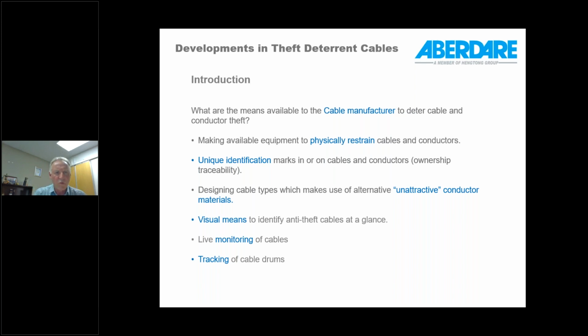So what can we as a manufacturer do to try and prevent cable theft? I think the first thing is that we can make available equipment to physically restrain cables and conductors. We know that some of these cables are being pulled out of the ground, cut in sections, and then hooked to a vehicle or pulling device and pulled out. So one can have these systems to restrain the cables that are in ground. Unfortunately, there's no such systems apart from traditional cable cleats to secure cables on racks.